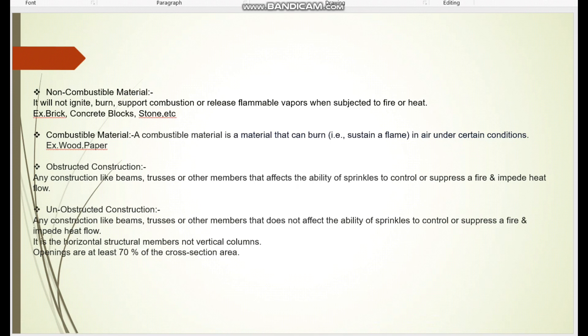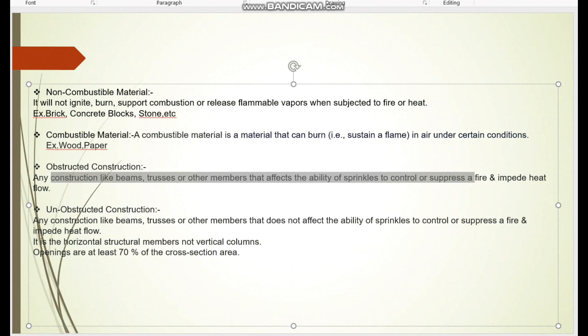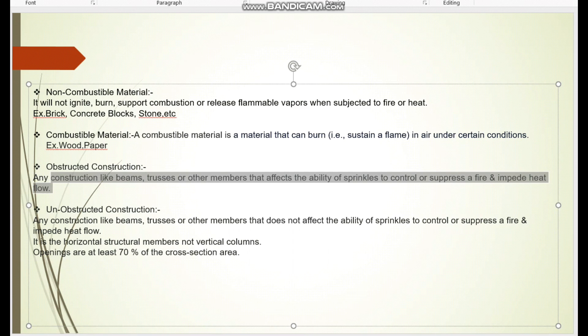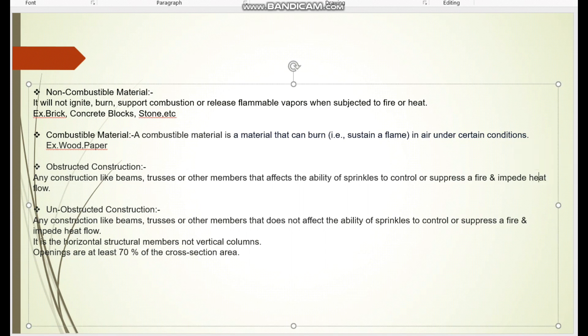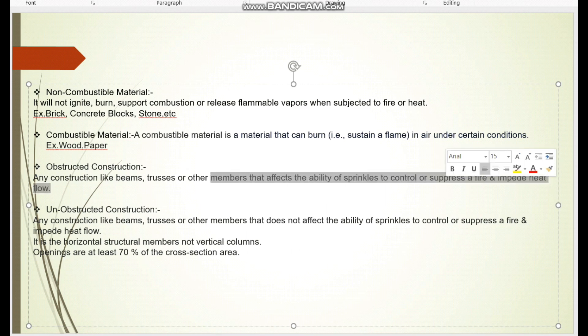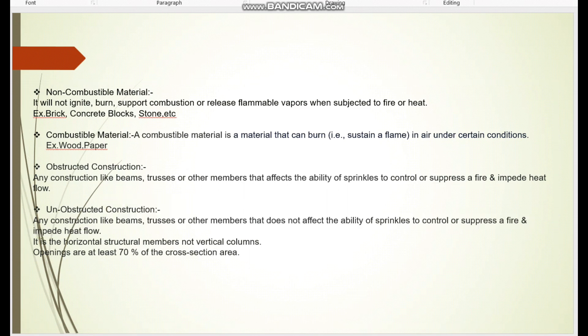Obstructed construction means any construction such as beams, trusses, or other structural members that affect the ability of sprinklers to control or suppress a fire and impair heat flow. A sprinkler activates when heat from the burning fire reaches that point, so heat flow must not be disturbed, and the sprinkler water discharge must not be obstructed. Unobstructed construction is the opposite — it does not affect sprinkler discharge capacity or impair heat flow.